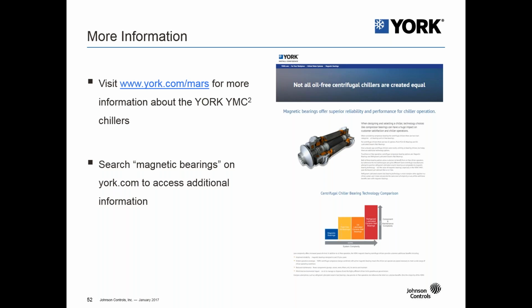But even places like California and Florida have well over 10% of their hours below 55 degrees, which is significantly more than the 1% of hours that the chiller would see at the design point. So we feel it's important to look at the entire operational map that the chiller will be able to run, so that you can review all the different operating points and maximize your efficiency by looking at everything that's available for the system.